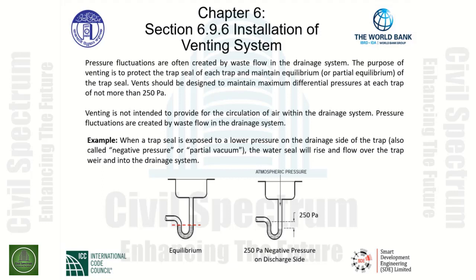Given here, if we have atmospheric pressure pushing downward in our drainage system on the building side of the trap, we can see that we have a differential happening within the trap. As seen here, we still have a trap seal that will provide protection for the building occupants. This information is good to analyze, good to implement, and for protection of the public.